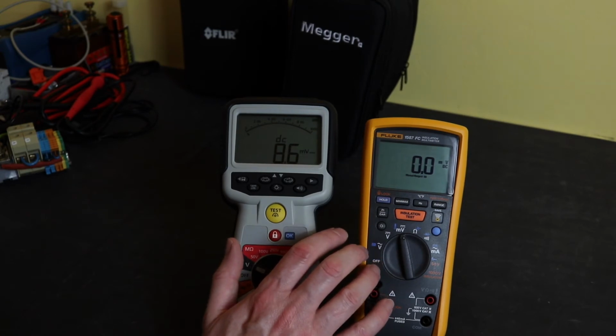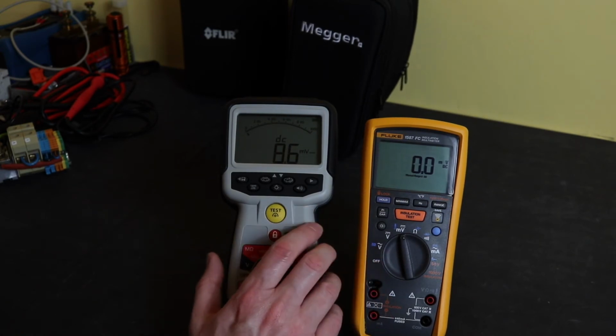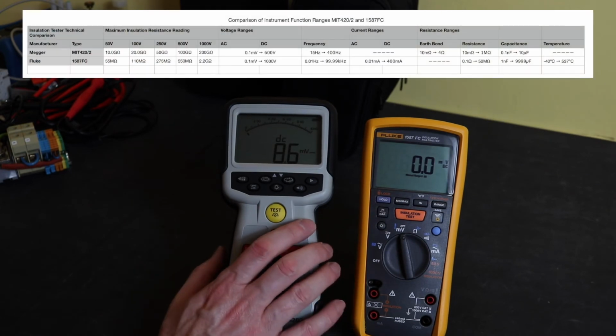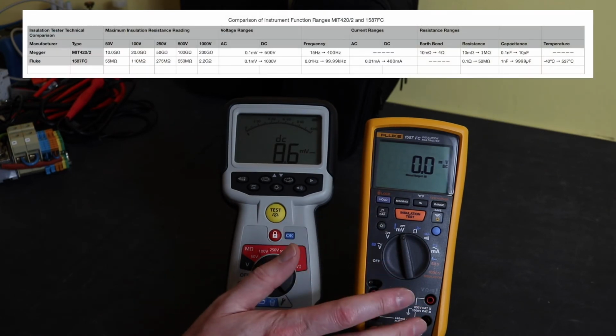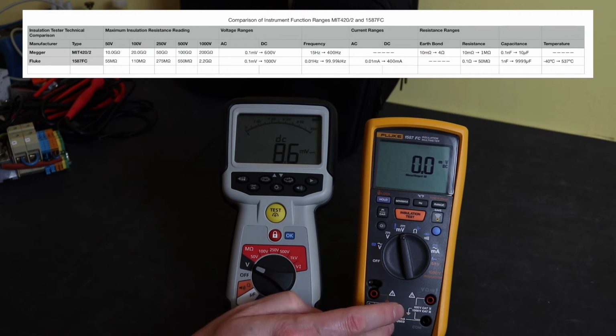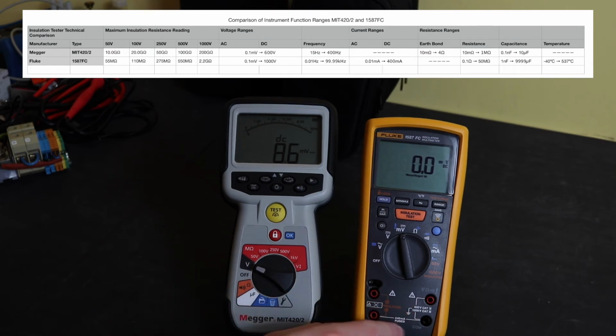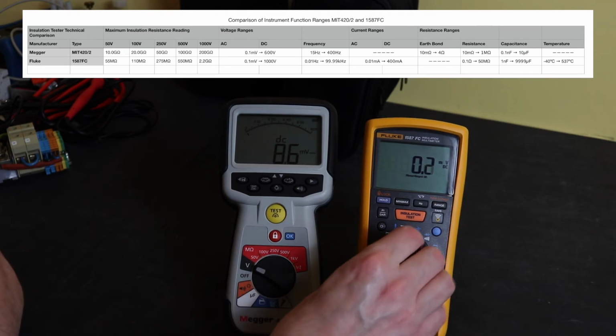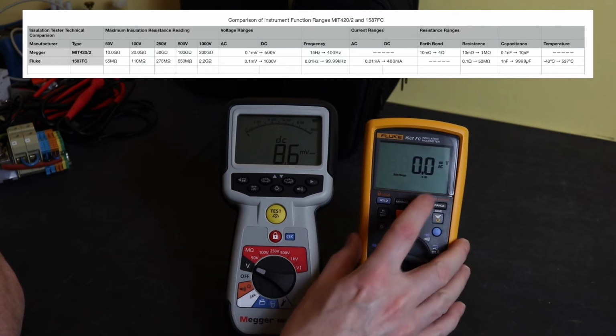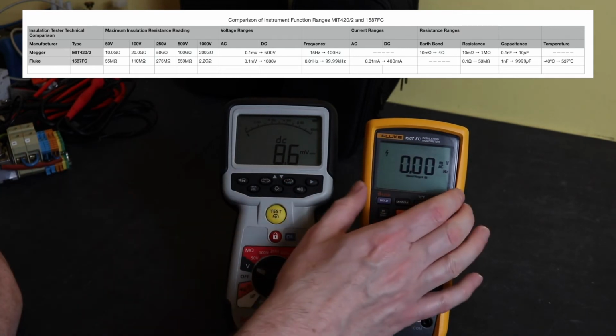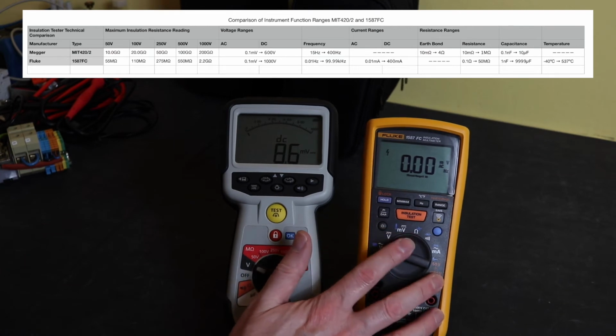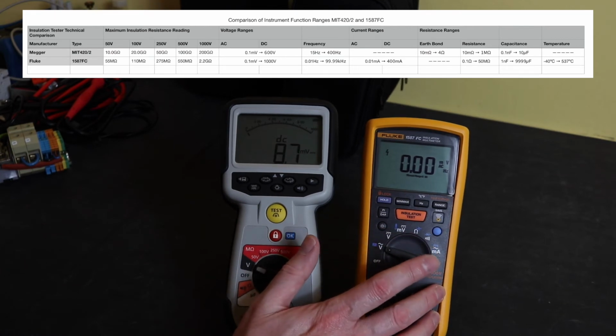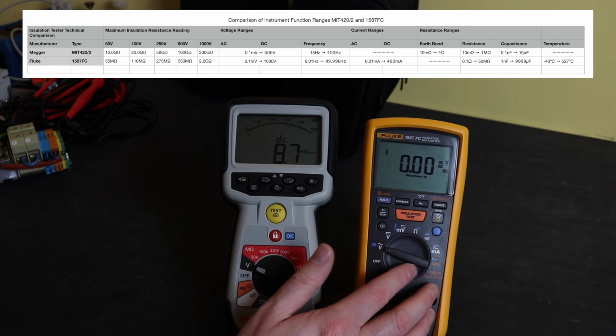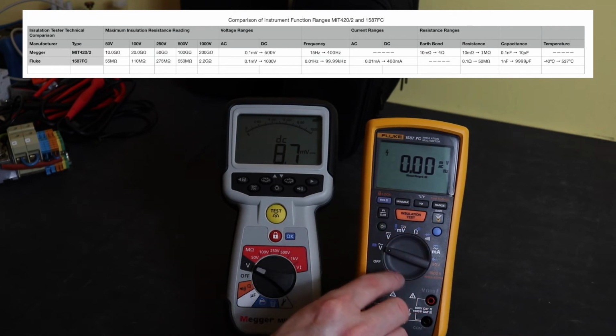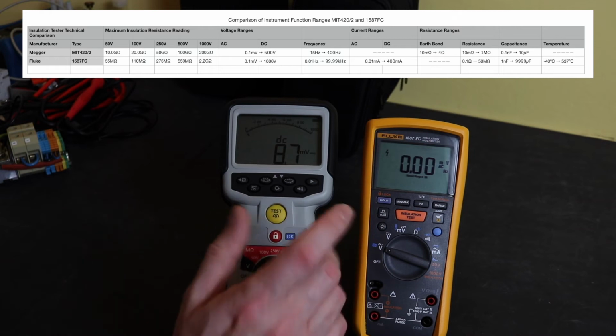In terms of voltage, the Megger will read 0.1 millivolts up to 600 volts, and the Fluke will measure 0.1 millivolts up to 1000 volts, and this is also a Cat IV instrument as well. What I also did miss back on the AC function, you can also go to Hertz, and you get the Hertz on the main display of the screen, and that will measure from 0.01 Hertz up to 99.9 kilohertz, so a reasonable range there, typical of a multimeter, I guess.